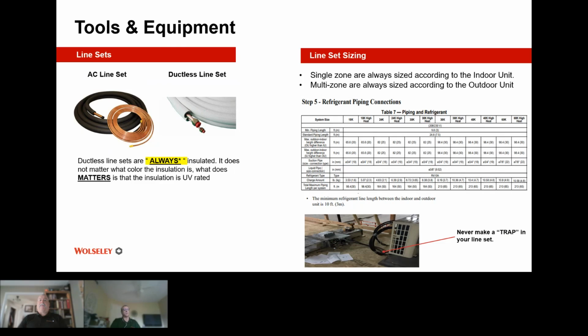The next thing I want to highlight here is that line set sizings are particular to the way that the ductless zoning is done. If you have a single zone, your line set is always sized according to the indoor unit. So if you have, for example, half-inch, quarter-inch line set connections on the indoor unit, you get a half-inch, quarter-inch line set, and you make your adjustments. If the outdoor unit is different, you make your adjustments at the outdoor unit, never at the indoor unit.